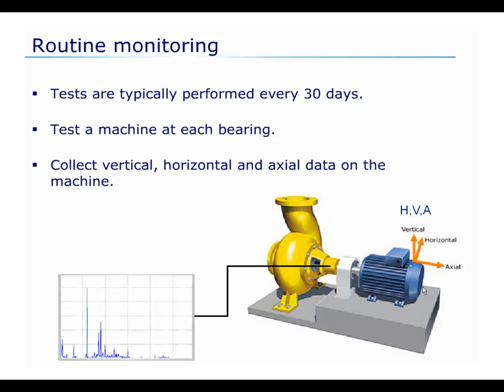Tests are typically performed every 30 days. A test at a machine is typically done at each bearing point. And because the machines move in three directions, we typically look at data in the vertical, horizontal, and axial directions so that we can help pinpoint which way the vibration is the most severe. We'll stop here and continue later.